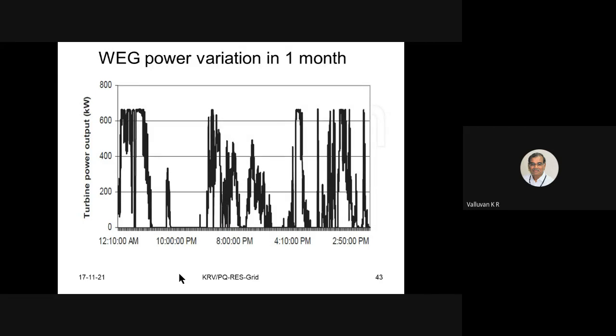For a specific case, let us see the power generated from a wind electric generator and how the power varies within a month. You can see the turbine output power in kilowatts. This is basically a 1.2 megawatt wind electric generator. The output power varied so much in one month's time. It produced a peak power of about 670 to 680 kilowatt, dropped to zero, or to only half of that or less, and keeps varying from time to time. How do we have that as a reliable power source for our grid system? It is a big issue.